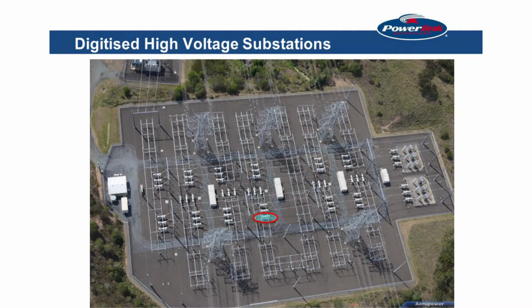You can see there are lots of switches which allow you to reconfigure the network, and the substation demountables, which is where the digital technology is - the brains of the substation live there. That's a change from how we were building them in the 90s, when we had one large building and put all the brains and protection systems in there, with about 4 large panels per bay. Whereas now in those areas we're getting a bay per panel, so we've reduced the footprint, which allowed us to go into these demountables, providing a lot of benefits. All of a sudden you don't have cabling from one end of the yard to the other - the cabling's much shorter, but it also gives a lot more flexibility when you're going to build.